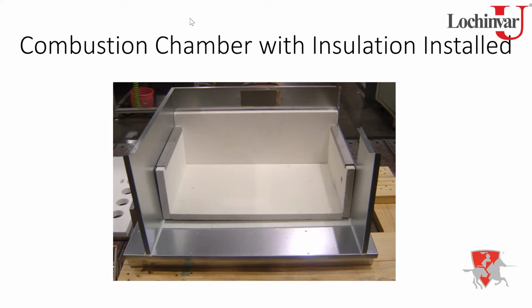If it starts to break down, chunks start to disintegrate or cracks start to form. That tile is what's protecting the sides of the panel from the heat coming from those burners in the combustion chamber and warping them. And once you warp the left, right, back side of that panel or the bottom, that's a new unit. Those panels are not replaceable. The only replaceable panels are the top and the front. So if something happens to those other sides, you're looking at a big issue. Do keep all that in mind.